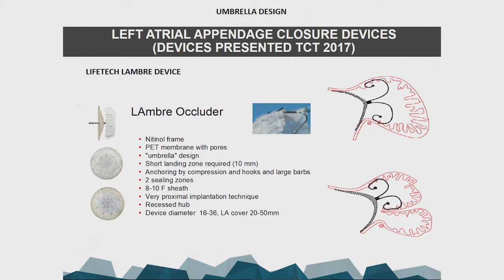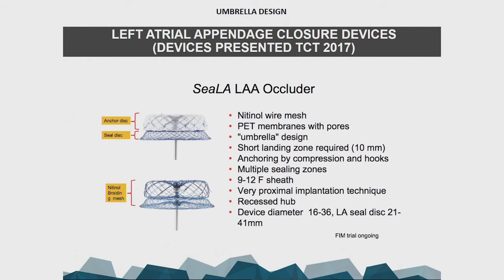And another interesting feature is that they have two sets of devices. So the one that you see on the right, on the upper part, is the conventional device, and in the lower part, it's a small lobe, small anchors with an oversized disc. So you can decide to implant the anchors in a small lobe, and then you have a very large disc that will cover the entrance of the LAA. And this is already available on our markets.